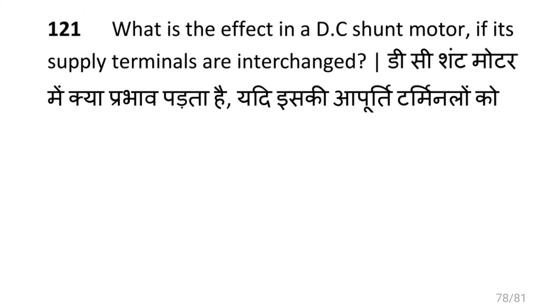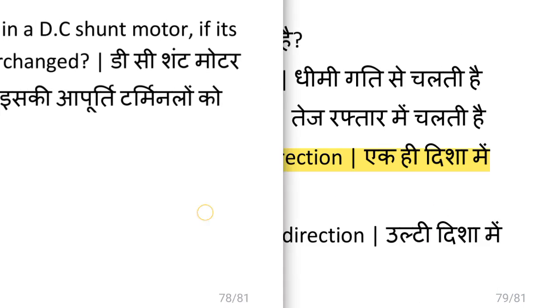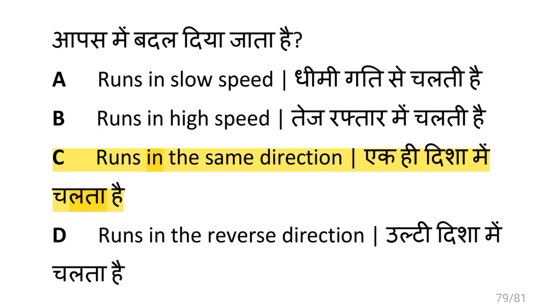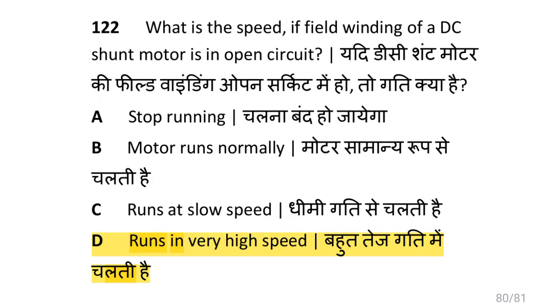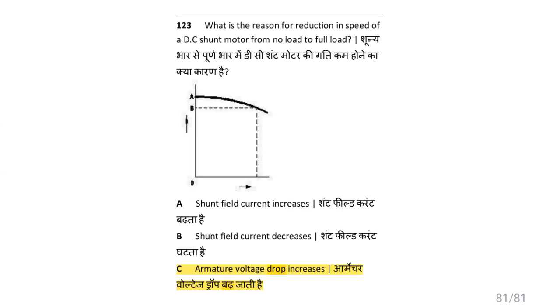What is the effect in a DC shunt motor if its supply terminals are interchanged? That is it runs in the same direction. What is the speed if the field winding of a DC shunt motor is in open circuit? Then it runs at very high speed. What is the reason for reduction in speed of DC shunt motor from no load to full load? That is armature voltage drop increases.